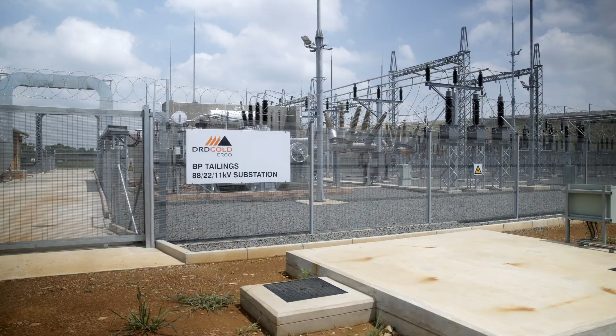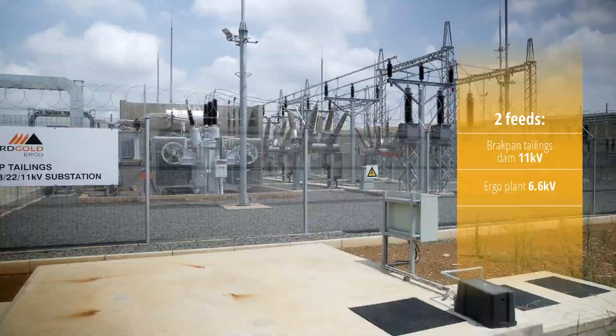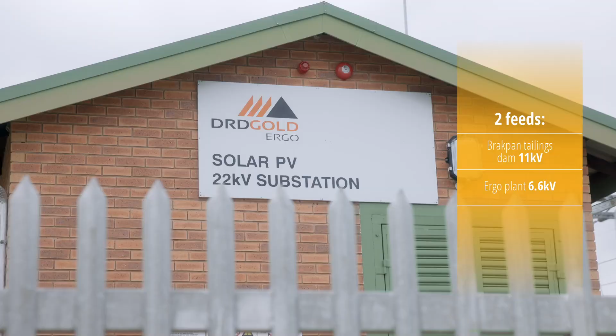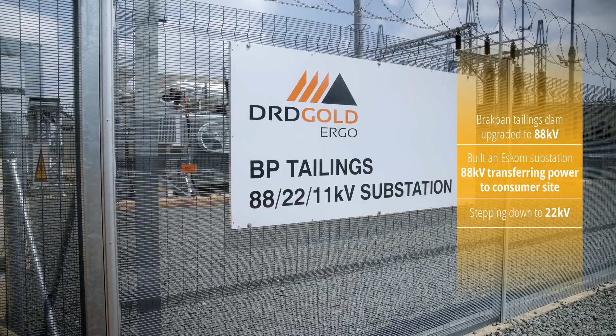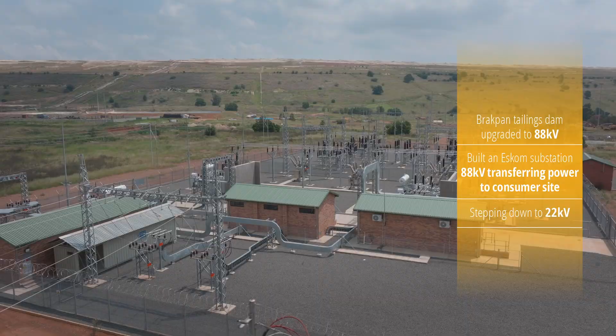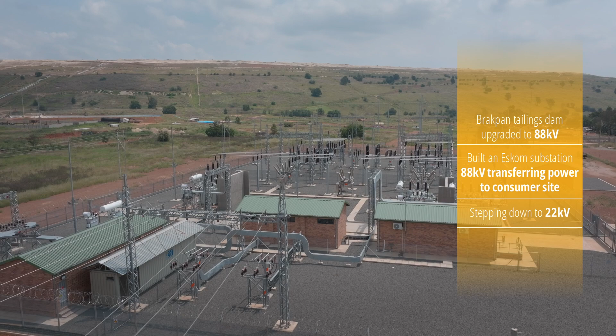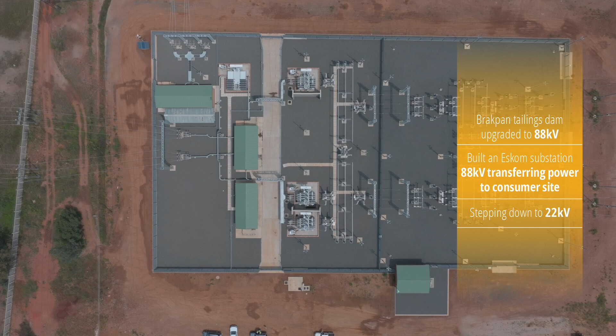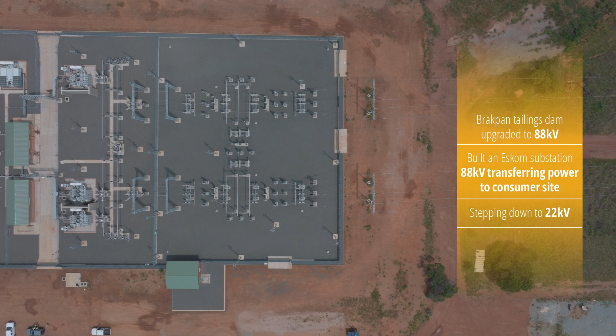Ergo at that stage had 2 feeds. It had 1 feed into the Brakpan tailings dam and 1 feed into the Ergo plant from Ekurhuleni. The Brakpan tailings feed was at 11 kV and the Ergo feed was at 6 kV. We then decided to upgrade the Brakpan feed to an Incomer 88 kV line, constructed an Eskom substation for 88 kV Incomer, transferring that power then to a consumer sub, which is our consumer sub at 88 kV, and then stepping that down to 22 kV.